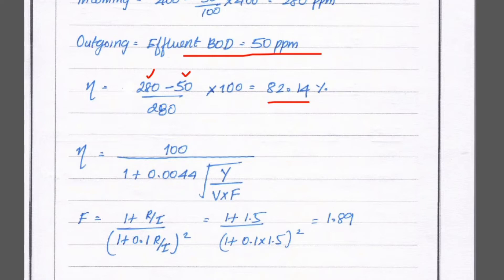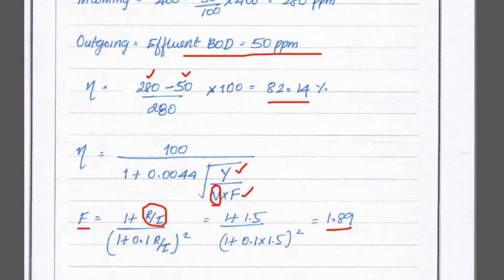The recirculation factor formula is: f = (1 + r/i) / (1 + 0.1 × r/i)². With r/i = 1.5, we get f = (1 + 1.5) / (1 + 0.1 × 1.5)² = 2.5 / (1.15)² = 2.5 / 1.3225 = 1.89. So the f value is 1.89.